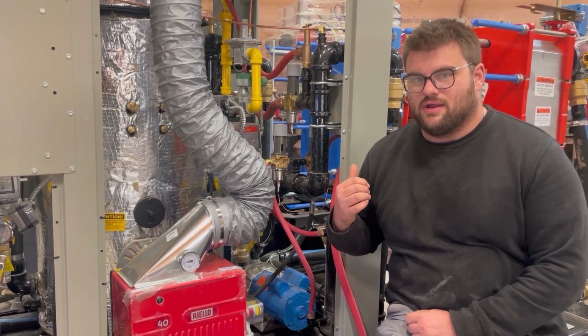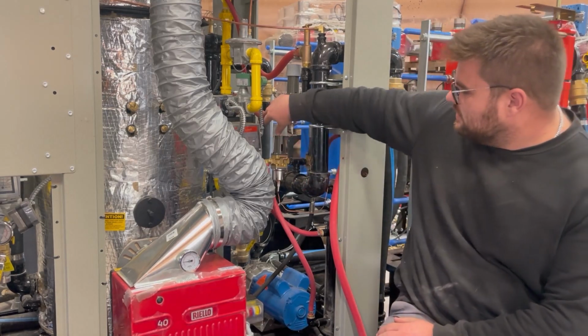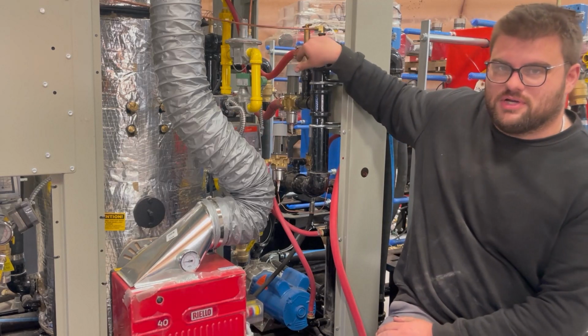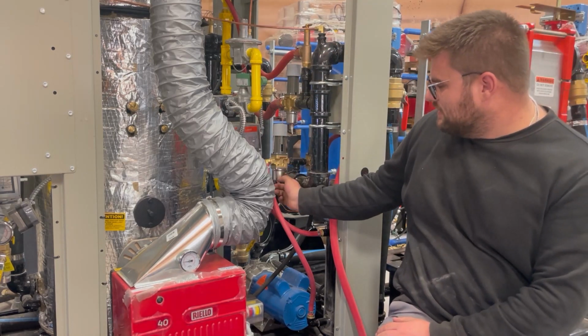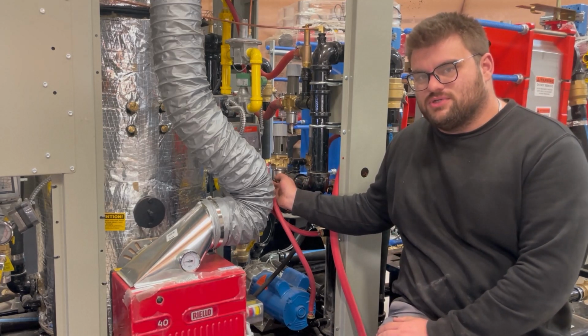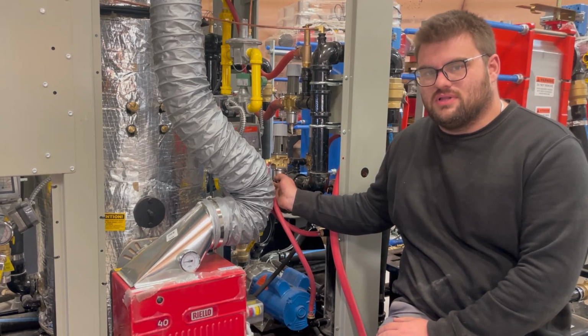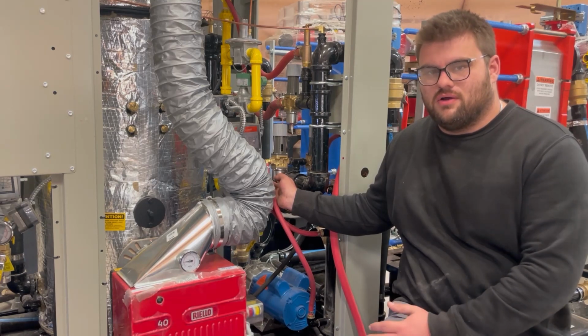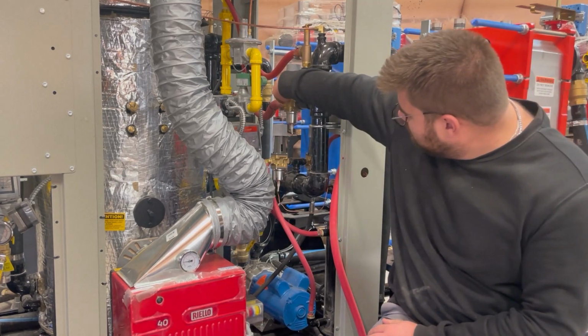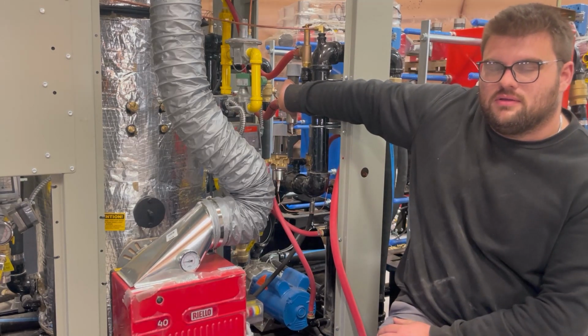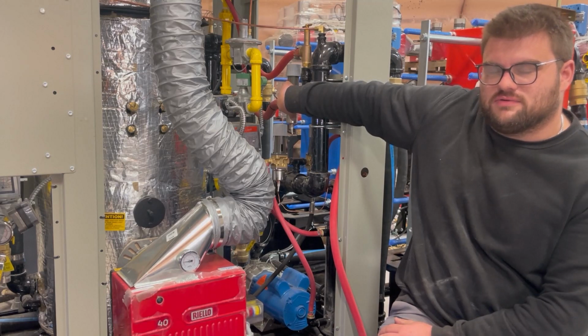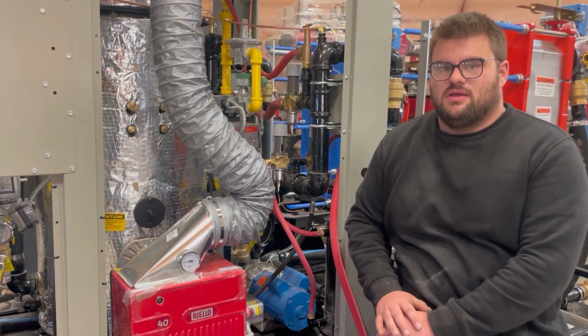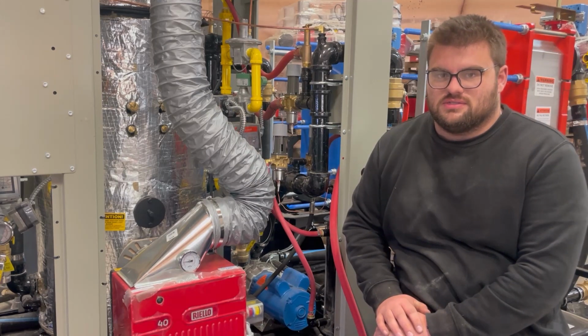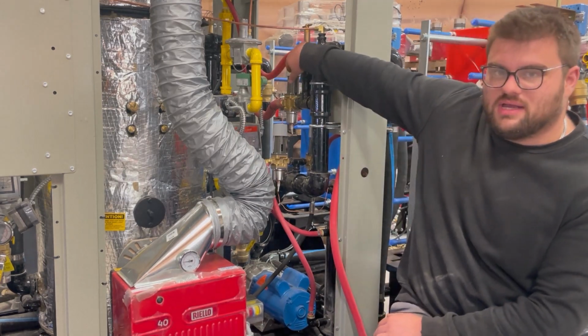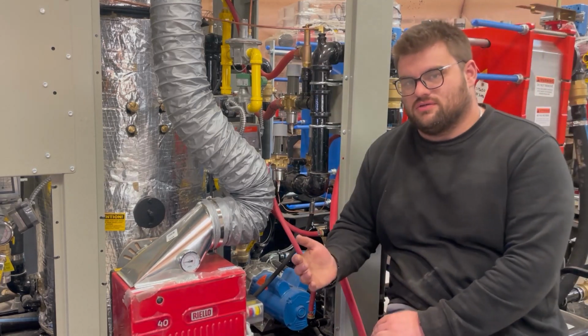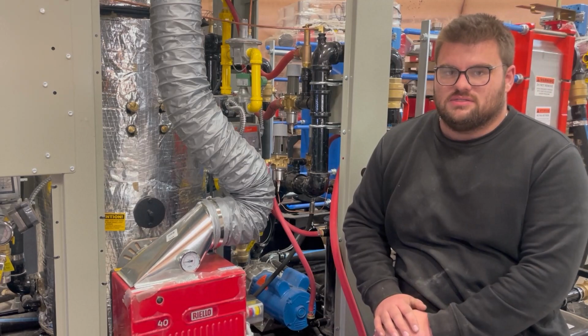Over here on the plumbing of the Dry Air Hydro Heat Pro, we have 3 temperature control valves as well as 1 pressure bypass valve. The temperature control valves regulate the air and fuel temperature and supply hot glycol to the preheaters to allow 70-degree air and fuel to run on the burner at all times. This temperature control valve here is a bypass, which allows glycol to run from the supply side to the return side of the unit at all times up to 140 degrees. Your pressure bypass supplies glycol from the supply to the return again, but it's to help with the deadhead situation.